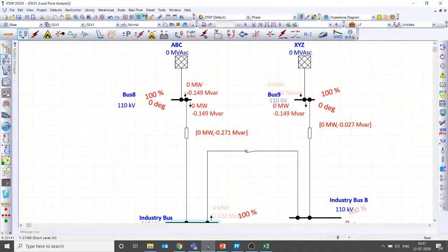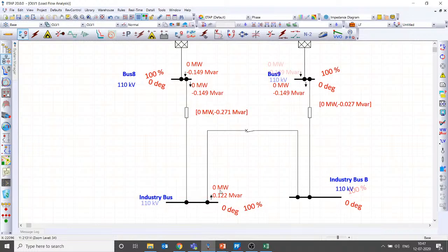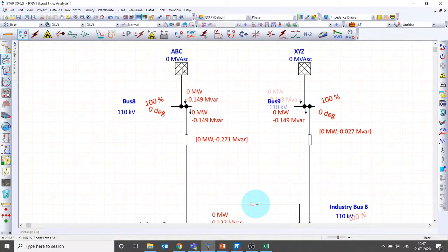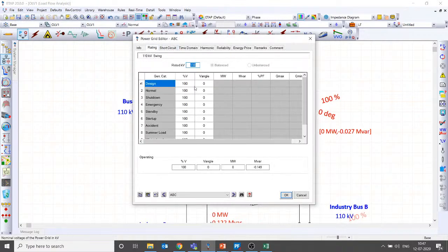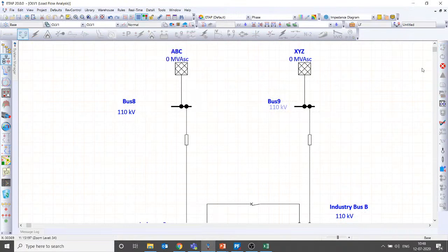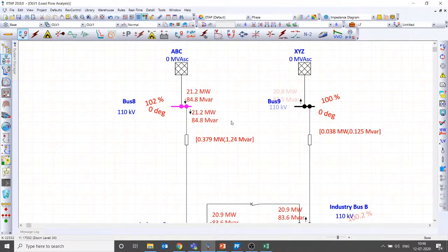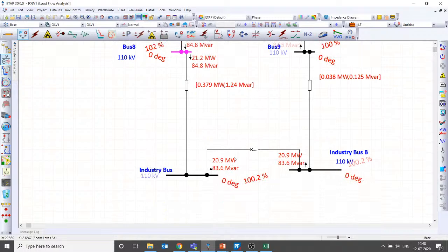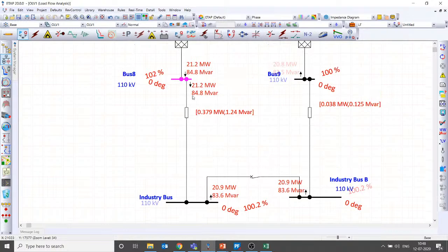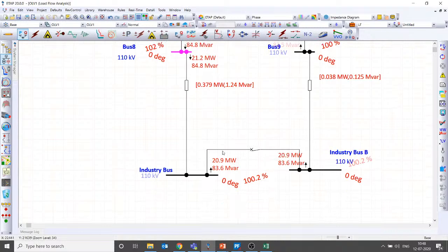Yes, so here you can see there is a power flow, 0.122 MVR, which is flowing in your industry substation even if you have not connected any loads. And this uncontrolled power flow will be much different when any one of these substation voltages is slightly different. For example, if I take one substation voltage as 1 or 2 percent different, then you can see a huge reactive power flowing via your industry substation, right? You can see about 21 megawatt and 84 MVR flowing via your industry substation, though I have not connected any loads in my industry.